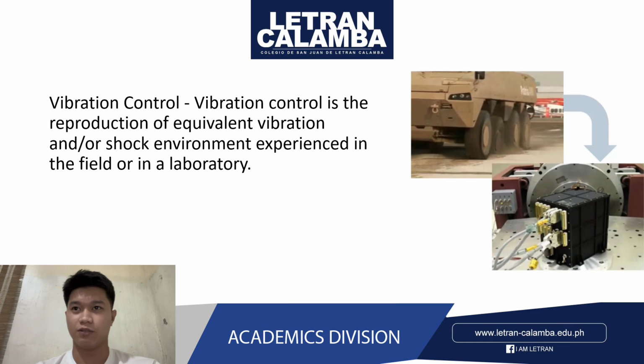Vibration control allows engineers to validate the reliability of their products through control testing. Vibration control is the reproduction of equivalent vibration and shock environment experienced in the field, in a laboratory.